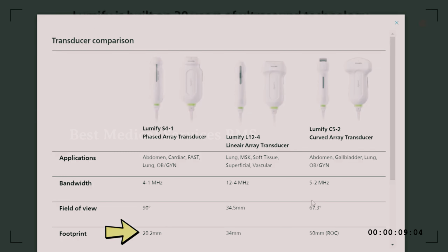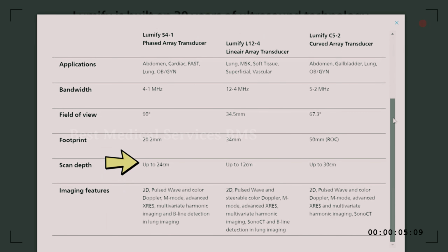The S4 has the smallest footprint, which is good for getting in those parasternal areas, and a pretty reasonable depth of 24 centimeters. The linear 12 has a long and skinny footprint of 34 millimeters, providing high resolution with a short 12 centimeter depth. And the C5 has a big old footprint with deep imaging up to 30 centimeters, exactly what we're looking for in a body probe.